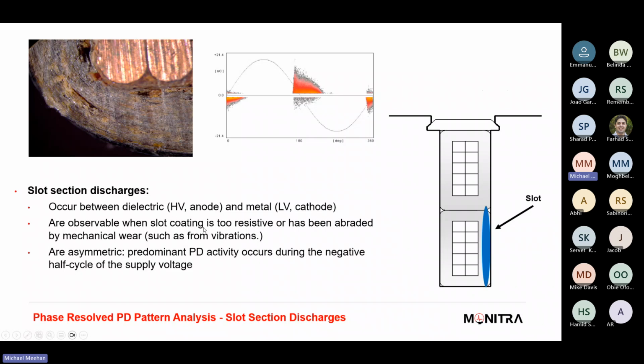So when slot coating is too resistive or has been abraded by mechanical wear, such as from vibrations, you'll get asymmetric PD patterns, or predominant on one phase versus the other. So on this particular case, you can see on the negative half cycle of the PRPD pattern, you do get that buildup of PD. So just to explain the PD pattern here, the darker orange is severity of pulses, so number of pulses. So with PD, there's a few different parameters that we look at, but in terms of the heat map, the number of pulses indicates the number of discharges, and obviously the more discharges, the more active a fault is.